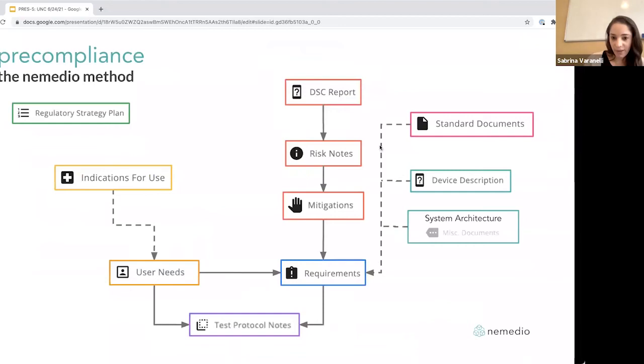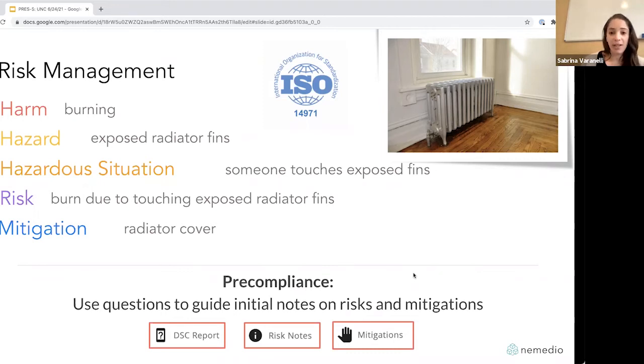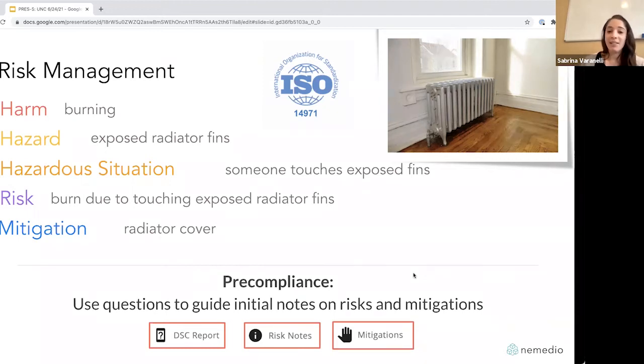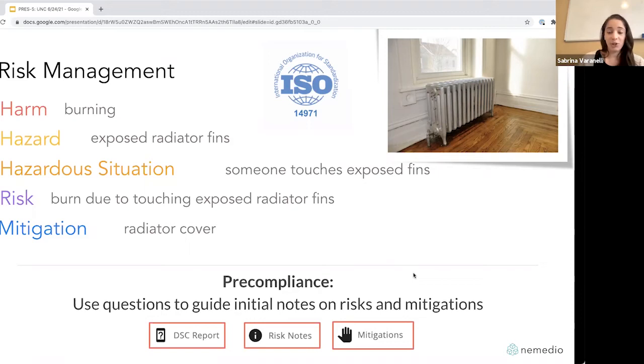The next chunk that feeds into requirements is risk management. Risk management is a massive undertaking for a med device company. There is a whole standard called ISO 14971 — very dense bedtime reading — that describes a systematic methodology for analyzing, determining, and mitigating risk in your medical device. I'll give you a preview of what you'll have to do in detail later, and then talk about what you can do early on to make full-blown risk management according to 14971 a lot easier when you're ready for it.